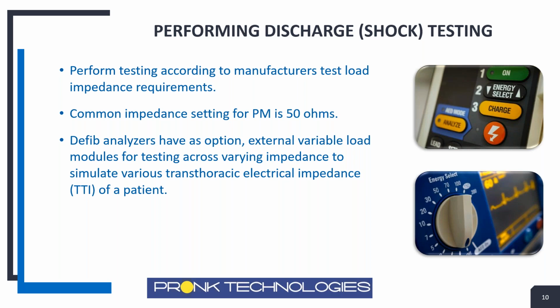Most all defibrillator analyzers have an option. It's an external variable load module that you can purchase that allows you to do discharge testing by varying the impedance to simulate the different TTI levels that can be simulated in a patient. You can find in the service manuals on some of the defibrillators that, depending on the load impedance you set your analyzer to, you could see various output readings. It won't always be exactly the same because the impedance of the patient is varying. But it will specify that the readings should all be within the specified tolerance of the defibrillator, though not always exactly the same reading.